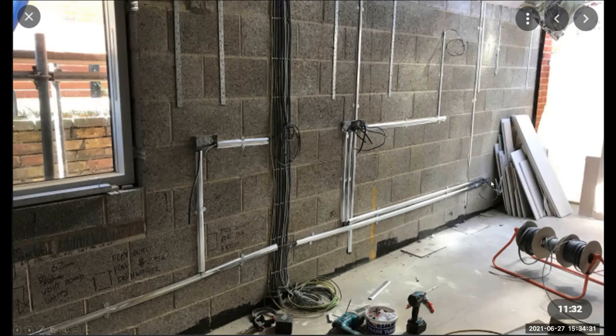I mean, look at the way this is coming all the way across there. You're not going to suddenly know that this changes direction here or here and comes into these cables here. This here actually goes down between two sockets, all the way to floor to ceiling. So you wouldn't know that that crosses all the way over. Again, look at this change of direction here. It's in the middle of nowhere. You wouldn't know that that was there.